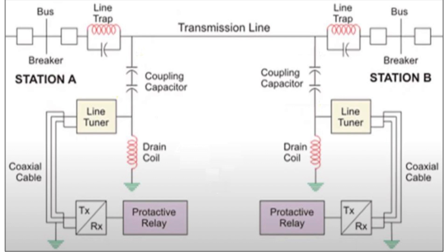The Line Matching Unit, or LMU, is a composite device that includes a drain coil, isolation transformer, tuning device, and earth switch. The LMU connects audio and radio frequency signals to the PLCC terminal and also protects the PLCC equipment from over-voltages caused by transients in the power system. Its tuning device, consisting of RLC circuits, acts as a filter, allowing only the desired frequencies to pass.